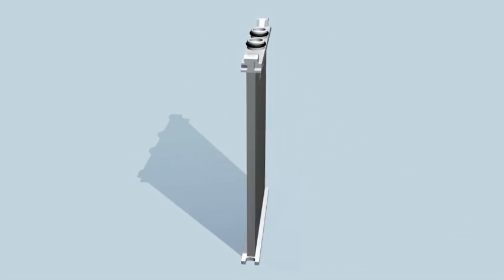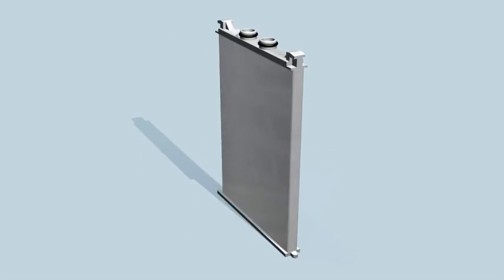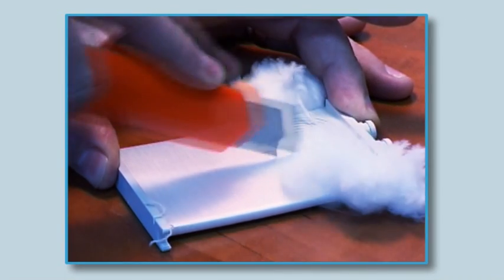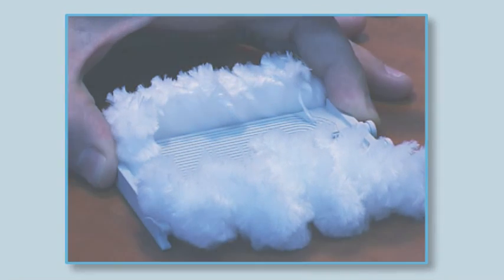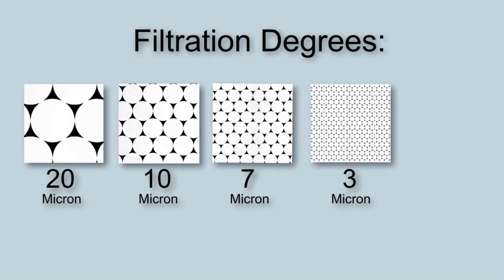The innovative filter media consists of a grooved rigid plastic body over which multi-layer textile threads have been wound. The thread type and tension, together with the number of layers, determines the quantity and the size of pores between threads, defining the filtration degree to 20, 10, 7, 3 and 2 micron.